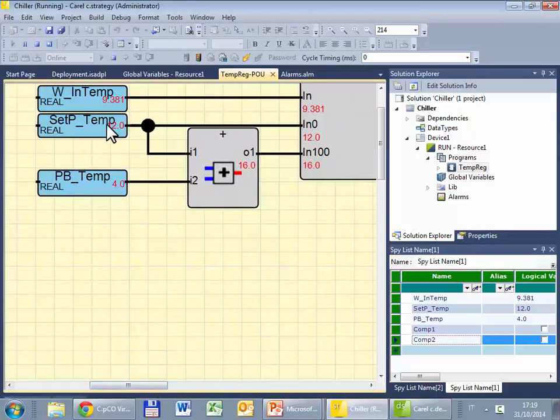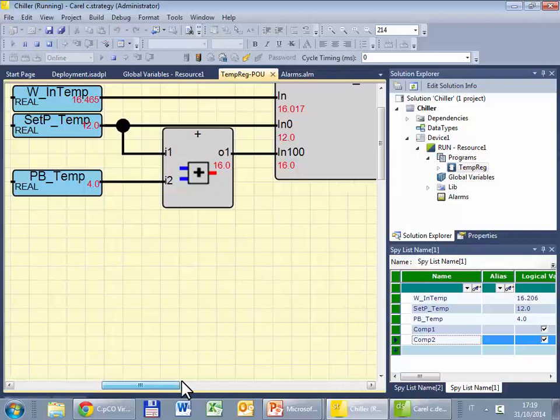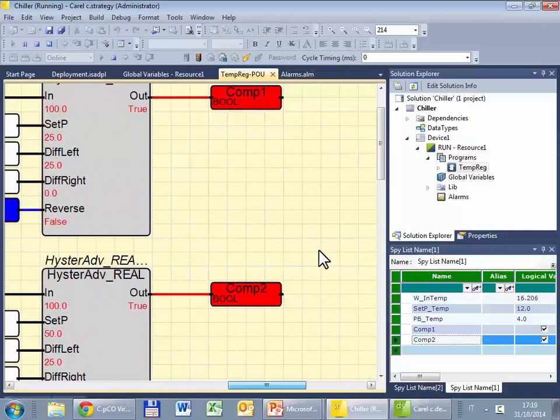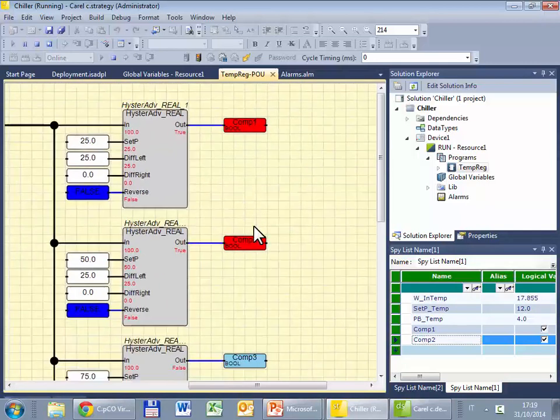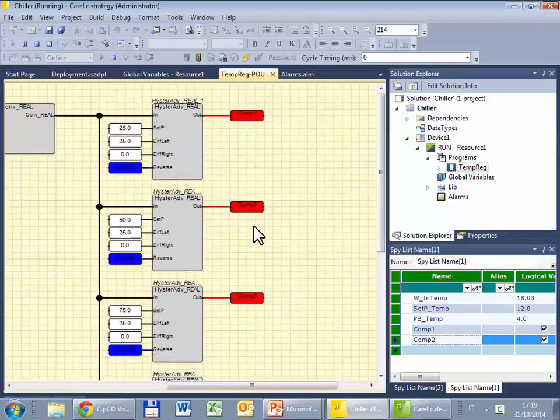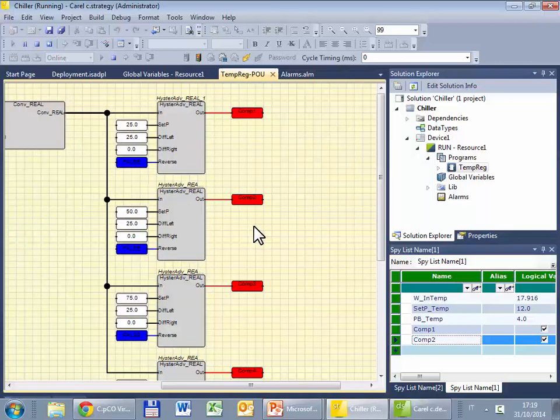Now here I can see the value that are in the controller. So the water inlet temperature is 9 degrees, now I am changing the temperature, you can see that it changes, probably you have the click of the relay, go down the temperature, 3, 2, 1, and 0 compressor.